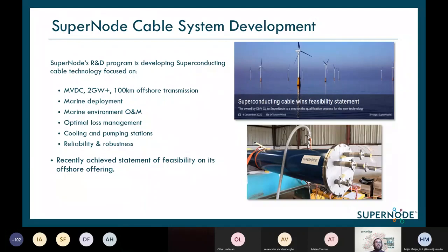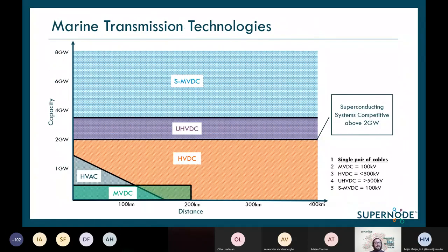Where we see the space for superconductors, we label them SMVDC, operating at a medium voltage of about 100 kilovolts. This compares to existing HVDC infrastructure, which goes up to about 2 gigawatts operating at 525 kV, and ultra HVDC, considered above that, up to 800 kV. The crossover point where superconductor benefits are truly exemplified is above 2 gigawatts in scale.